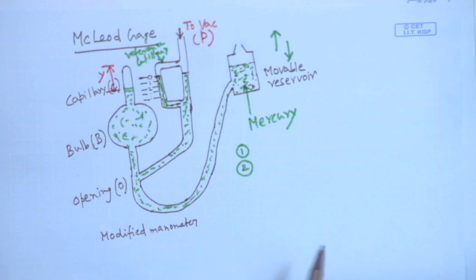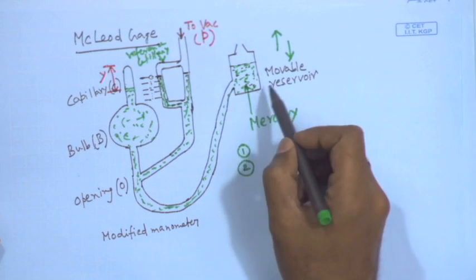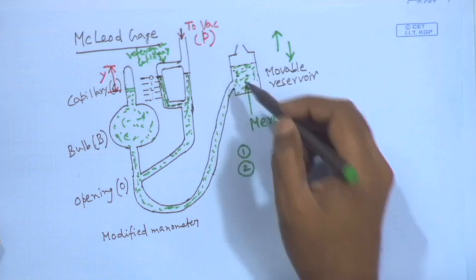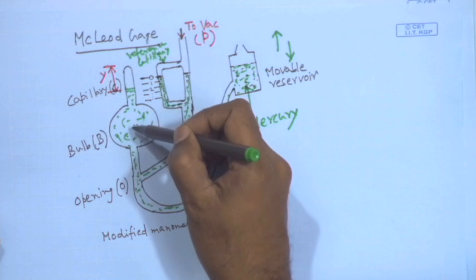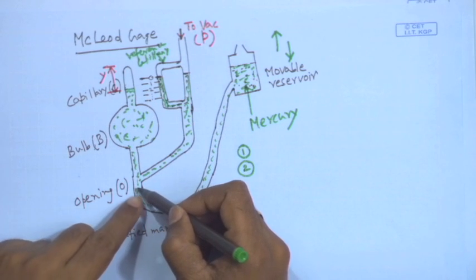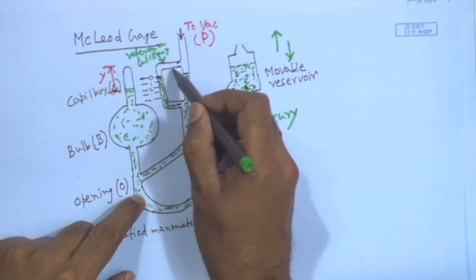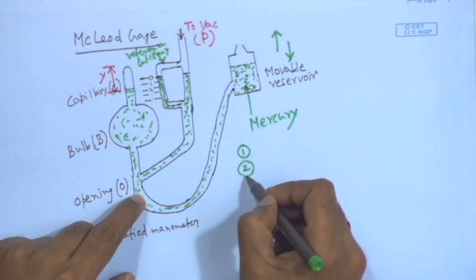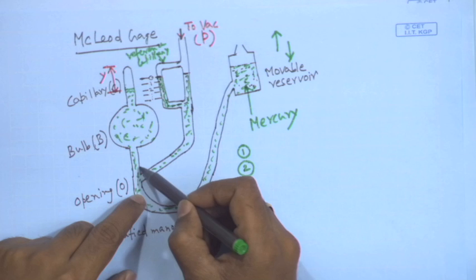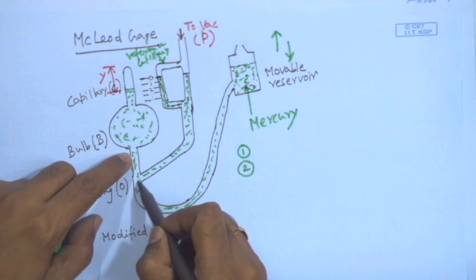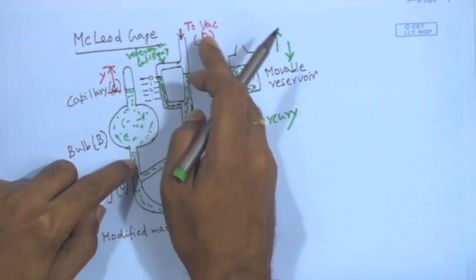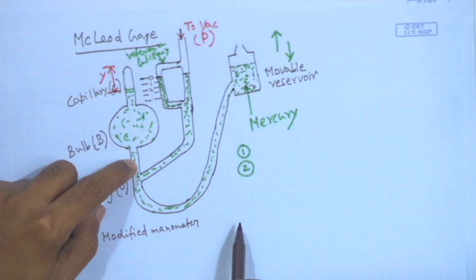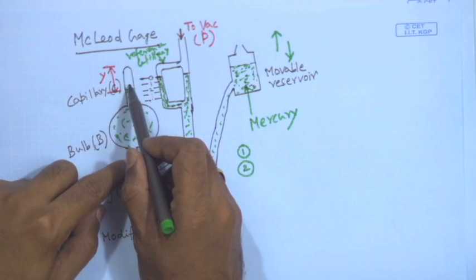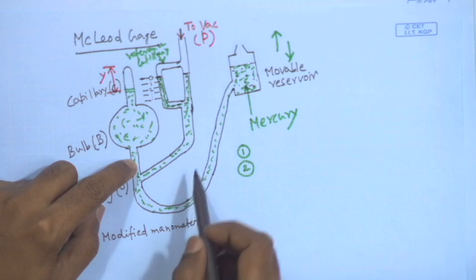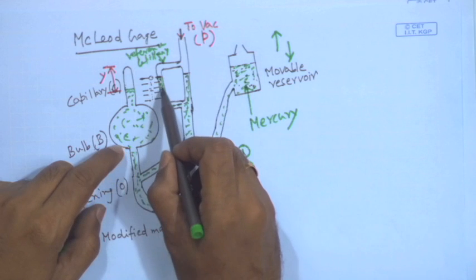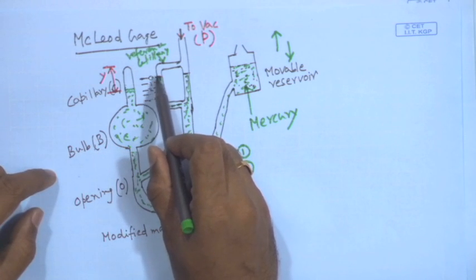So, the measurement has two major steps. In the first stage, the movable reservoir is lowered, and this is connected to a vacuum or low pressure source, such that the mercury level falls below point O. In that case, the entire capillary, bulb, reference capillary etcetera is connected to the same pressure source. In the second stage, I raise the movable reservoir. So, the mercury level keeps going up. When it crosses the point O, this part is now disconnected from the low pressure source. So, in fact, the gas inside is being compressed. I continue to raise the movable reservoir until the mercury level in the reference capillary touches the 0 of the scale.